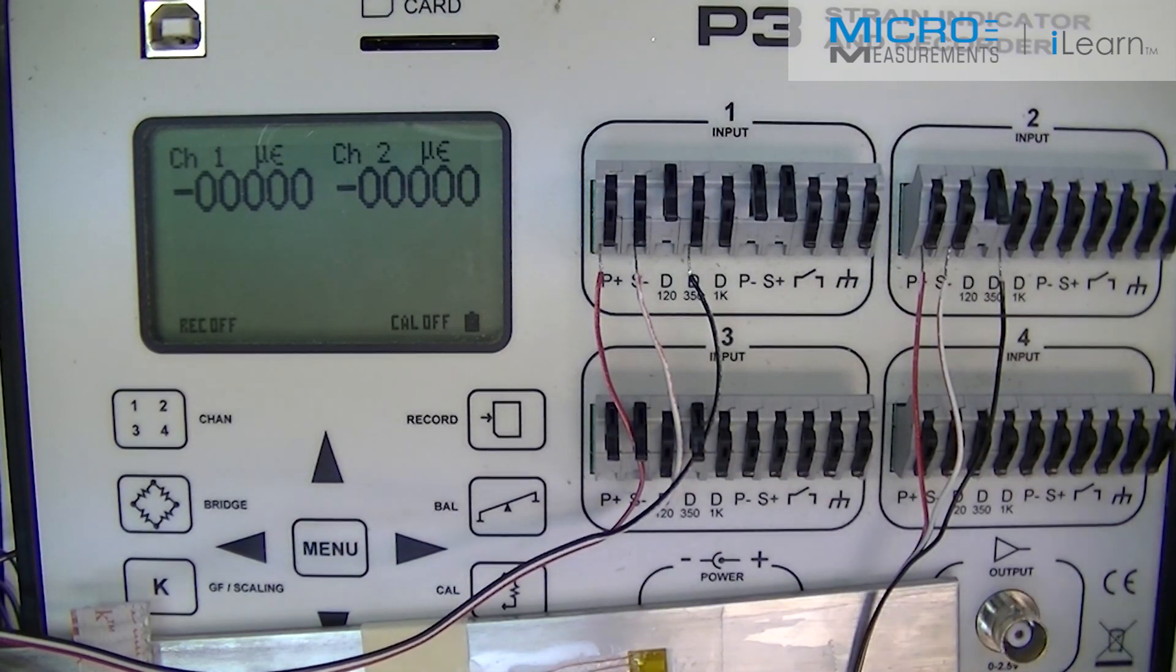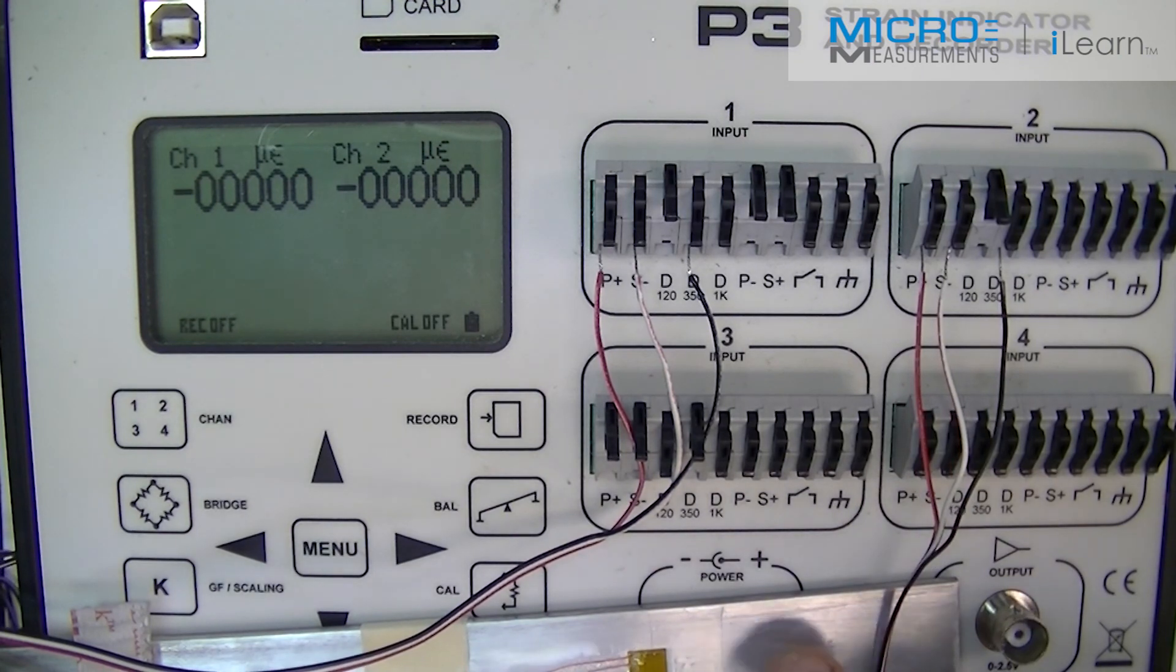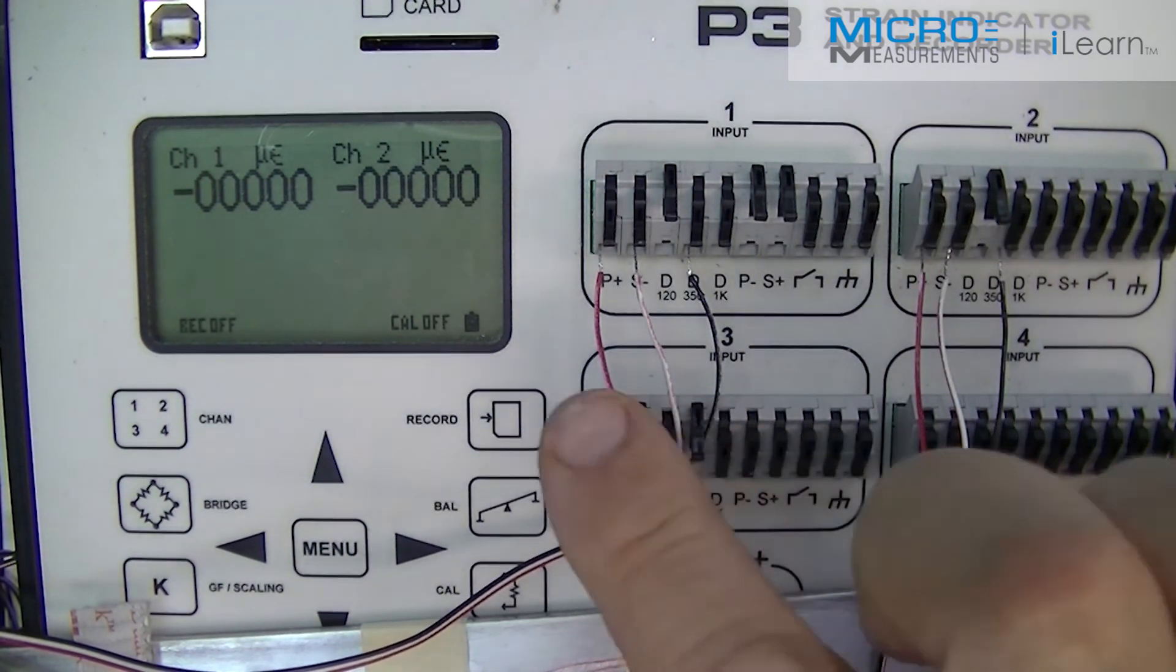The test of a strain gauge installation is zero return. When a gauge is bonded to a good spring-like material with a very linear elastic region, the material behaves like a spring. Under low loads, low strains, as I strain it, it should snap back to zero. Right now, the strain gauges are both indicating zero microstrain.